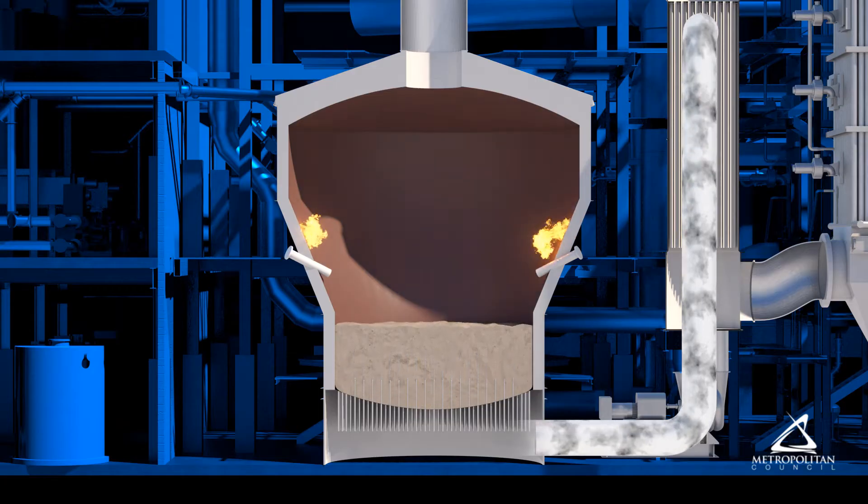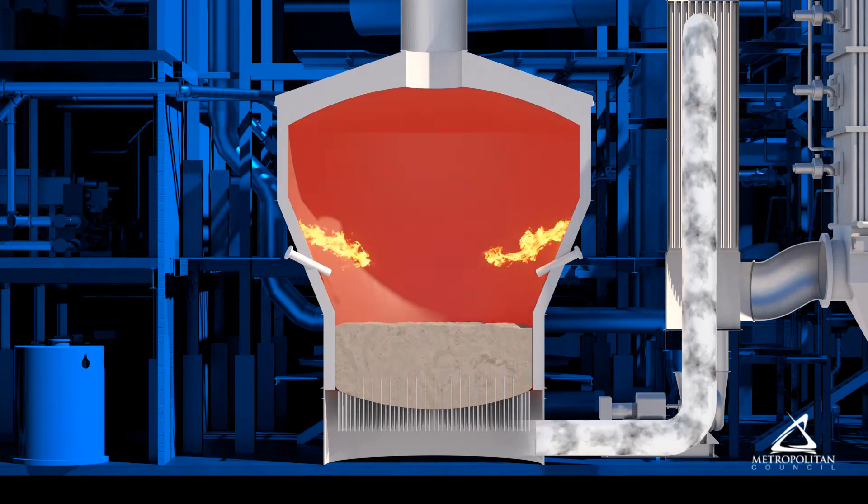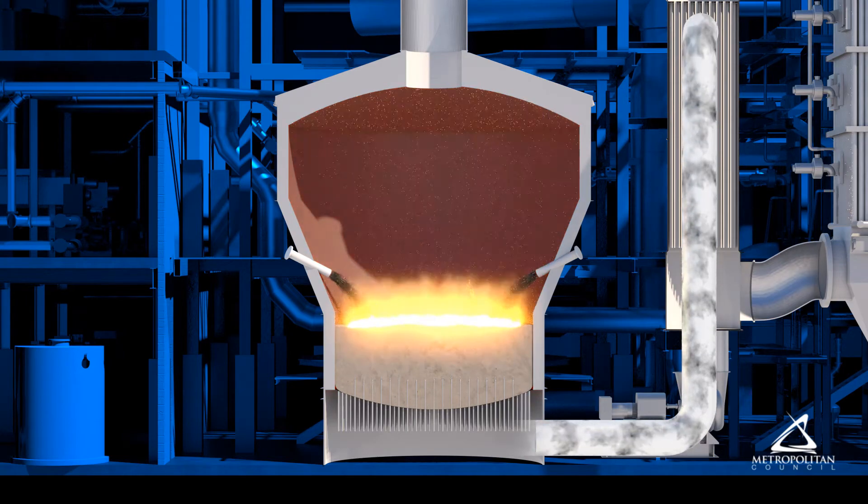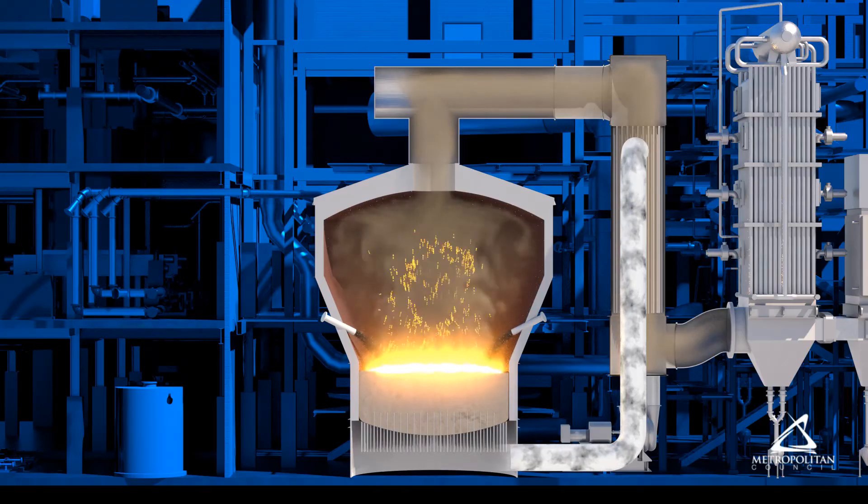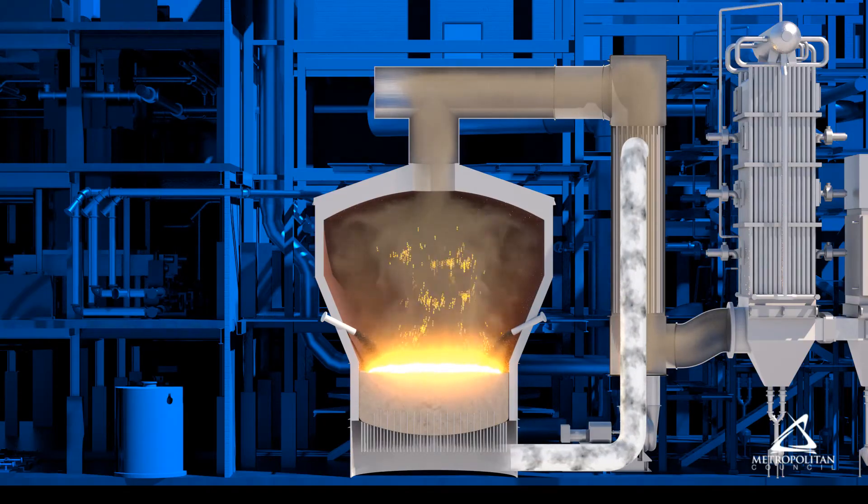We use natural gas for heat up when turning on an incinerator that has been shut off for maintenance. Like adding wood to a campfire, biosolids fed into the fluid bed incinerator combust when it reaches 1,375 degrees Fahrenheit. That's hot!